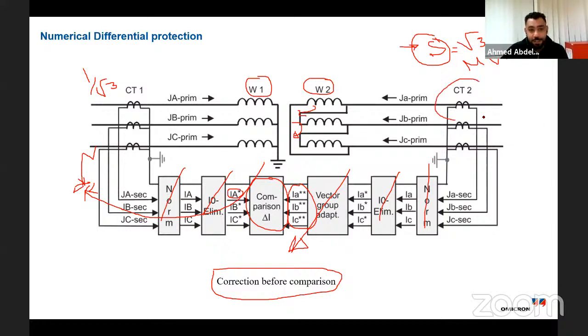But let us say something. I'm pretty sure that the CT ratio here is not identical to the CT ratio here, or the accuracy of this CT is not identical to the accuracy of this CT. Second thing, the resistance here is not equal to the resistance in this loop or this bus. So many parameters. So what I need to do is define a minimum operating differential current to avoid operation of my protection relay in a stable condition. I should reach this value to think that, okay, it might be a fault due to this differential current, but it's not sure. I'm not sure.